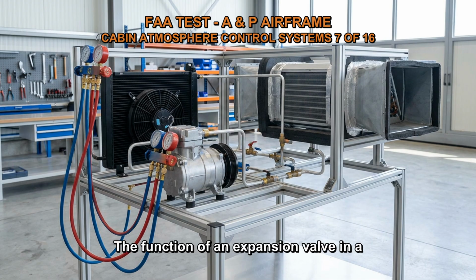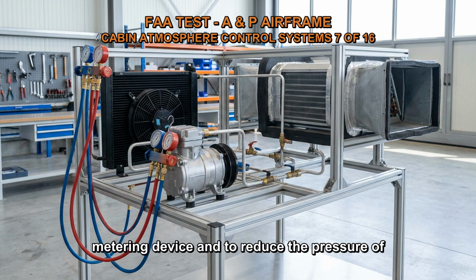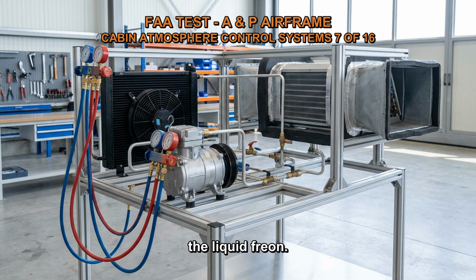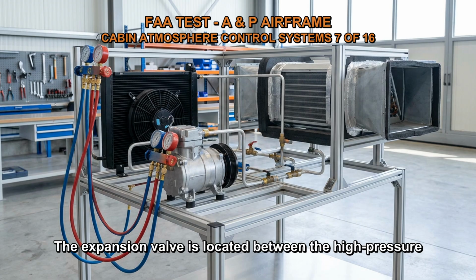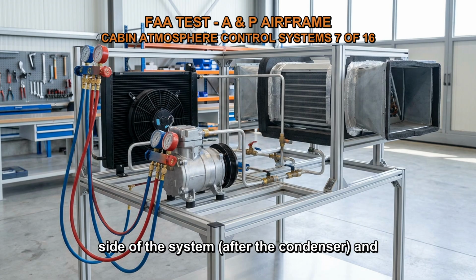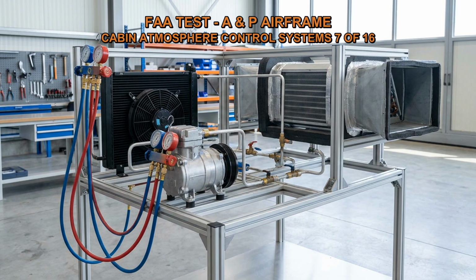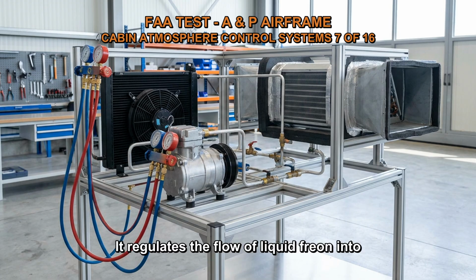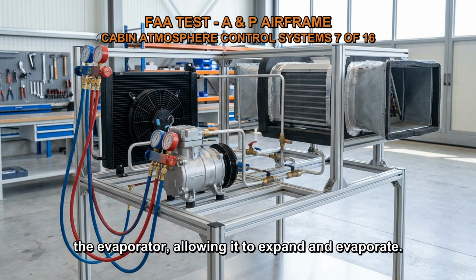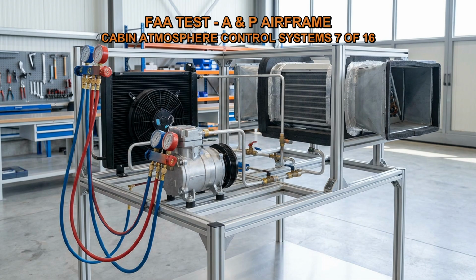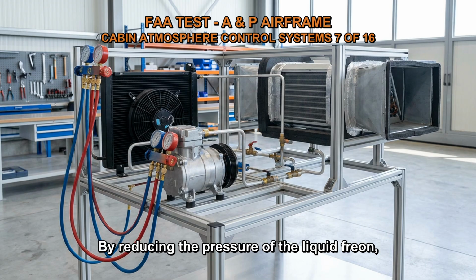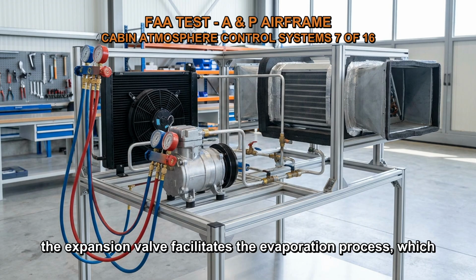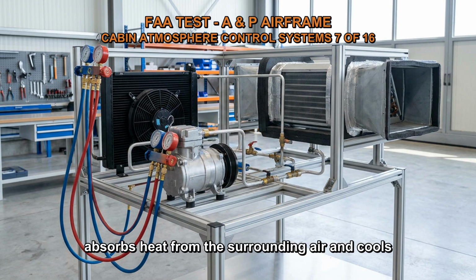The function of an expansion valve in a Freon cooling system is to act as a metering device and to reduce the pressure of the liquid Freon. The expansion valve is located between the high-pressure side of the system, after the condenser, and the low-pressure side, before the evaporator. It regulates the flow of liquid Freon into the evaporator, allowing it to expand and evaporate. By reducing the pressure of the liquid Freon, the expansion valve facilitates the evaporation process, which absorbs heat from the surrounding air and cools the cabin.